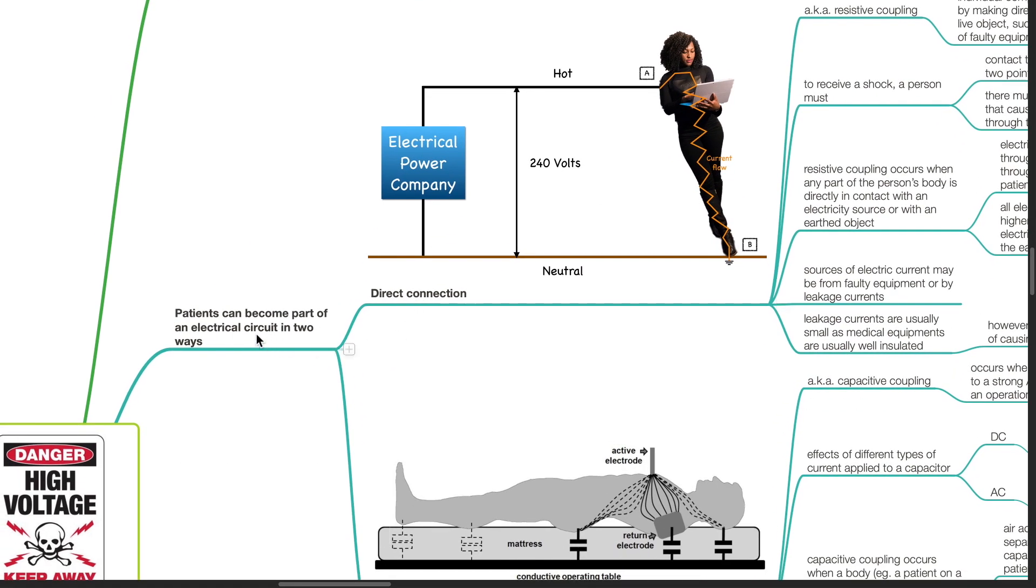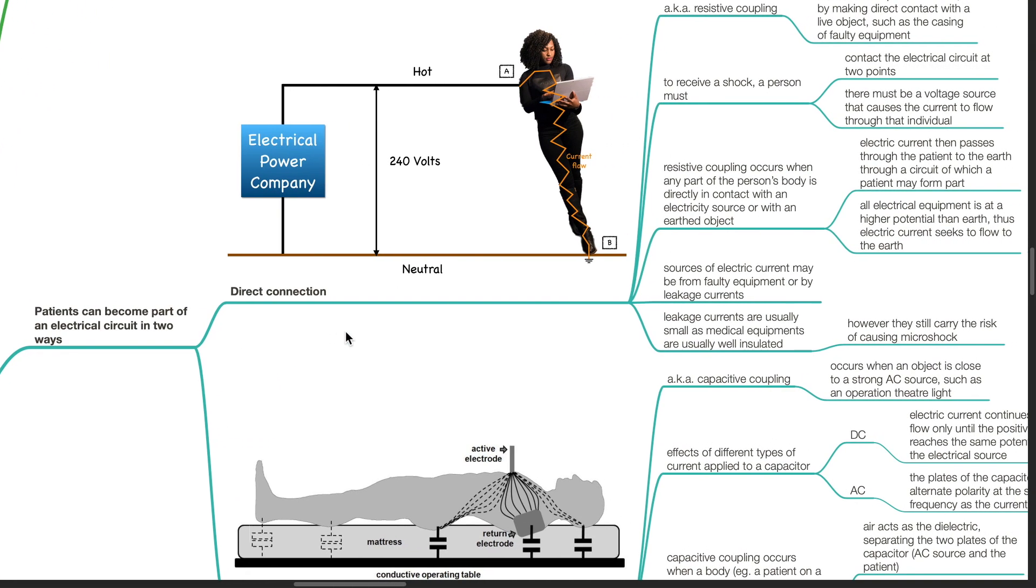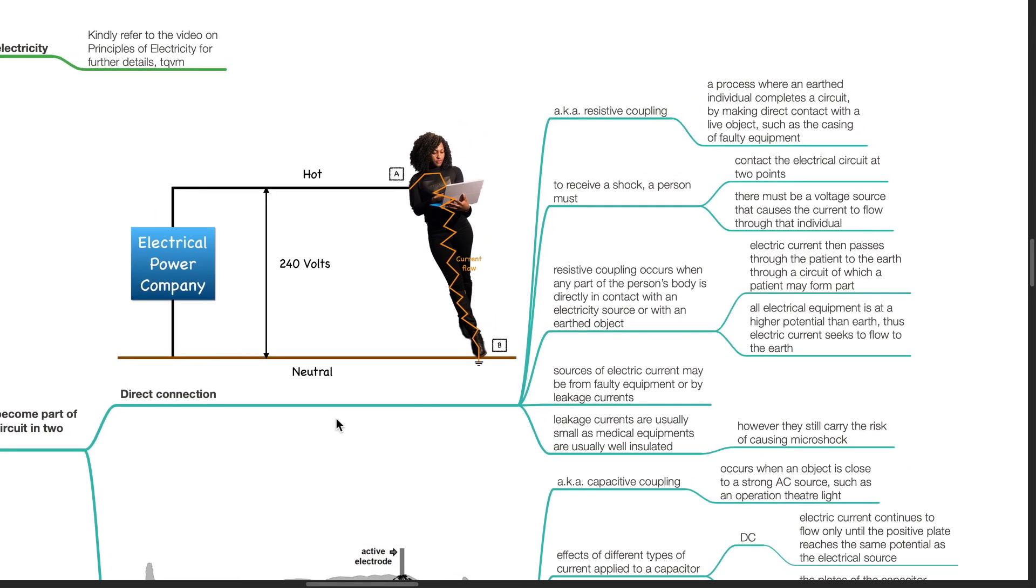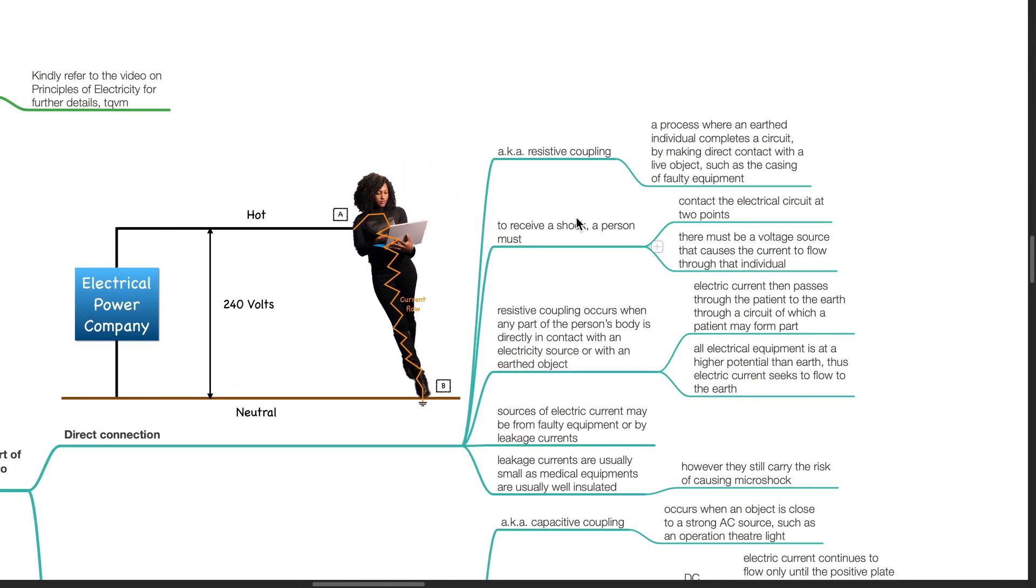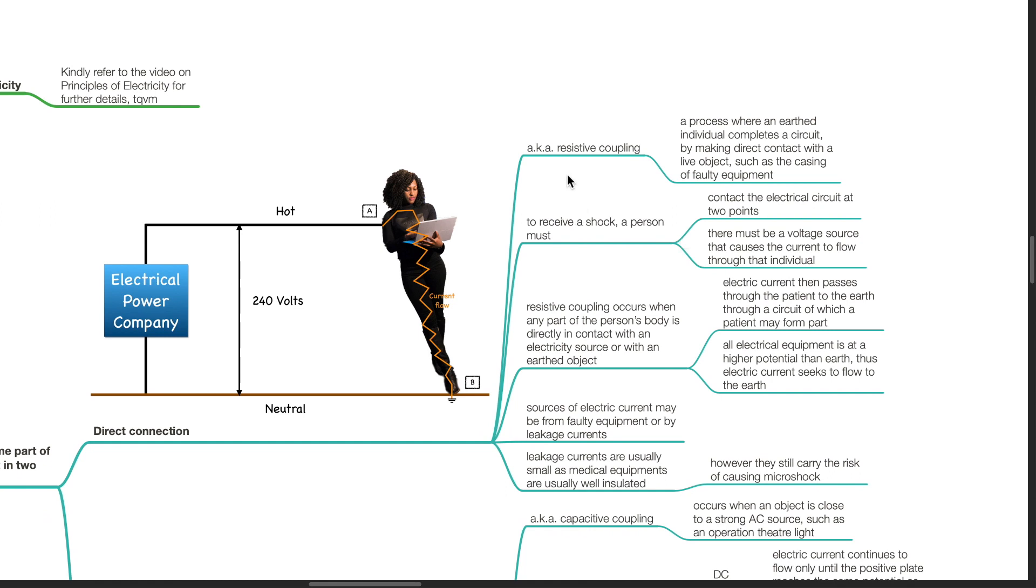The patient can be part of an electrical circuit in two ways, via direct or indirect connection. For direct connection, also known as resistive coupling, this is a process where an earthed individual completes a circuit by making direct contact with a live object, such as the casing of faulty equipment.